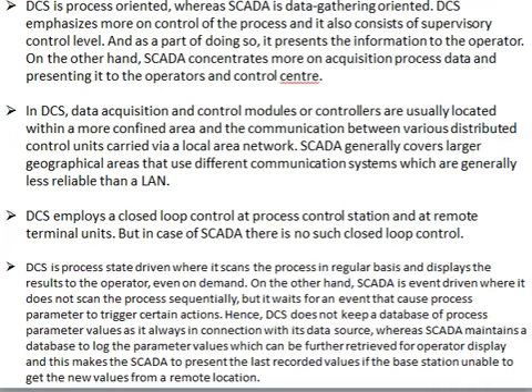DCS is process-oriented, whereas SCADA is data-gathering-oriented. DCS emphasizes more on control of the process, and it also consists of a supervisory control level. As a part of doing so, it presents the information to the operator. On the other hand, SCADA concentrates more on acquisition of process data and presenting it to the operators and control center.